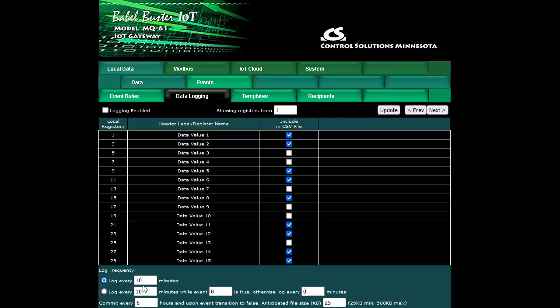You come down to the bottom and tell it to log every so many minutes or if you want the logging rate to change based on some event that's currently in effect then you say log at a certain rate while a given event number is true, otherwise log at a different rate. Right now we're logging automatically every 10 minutes.